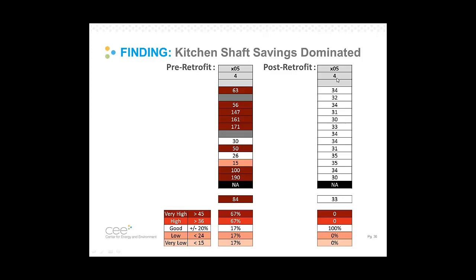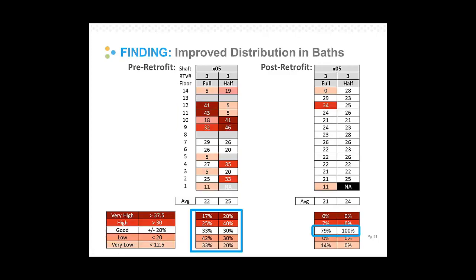You can see pre-retrofit, a lot of dark reds, a lot of high airflows, a lot of energy saving potential. After we installed the fixed orifices and turned down the fans, you can see this shaft is 100% within good or tolerable airflow levels. So great improvement, lots of energy savings here.